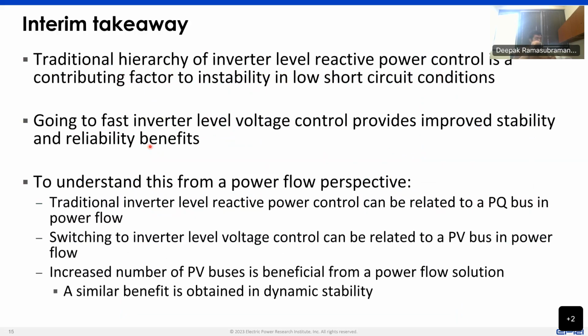Now, if you have to understand this from more of a power flow perspective, you can think of traditional conventional control of an inverter, which has active power and reactive power control at the inverter level, as a PQ bus. And if you switch to inverter level voltage control, which would be the enhanced IBR, think of it as a PV bus. And we know, when we are trying to solve power flow solutions, that if we have more PQ buses in the network, the chances of getting a converged power flow solution reduce. If you have more PV buses in the network, the chances that you have a converged power flow solution increase.